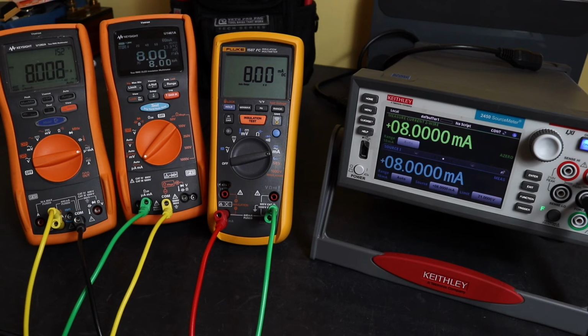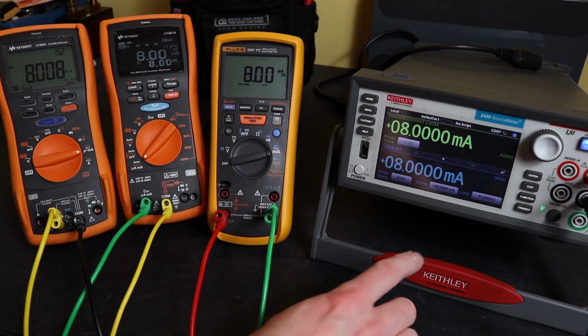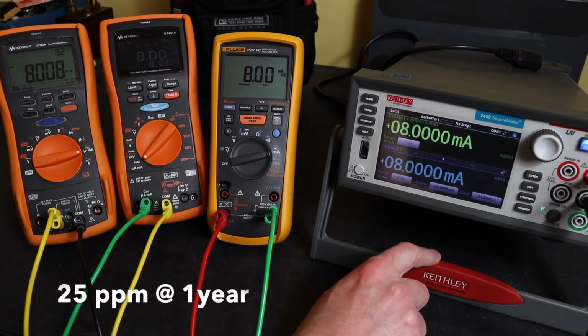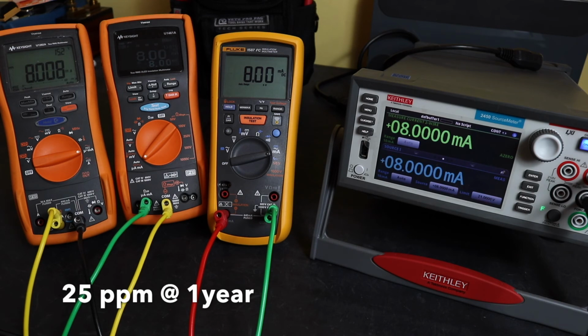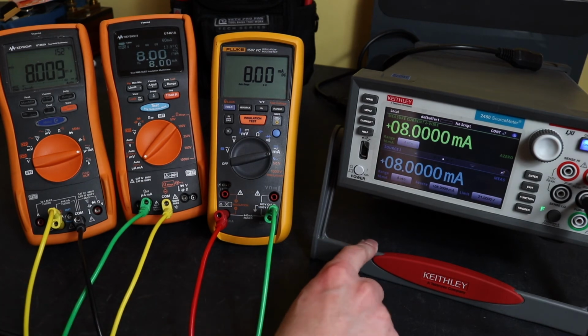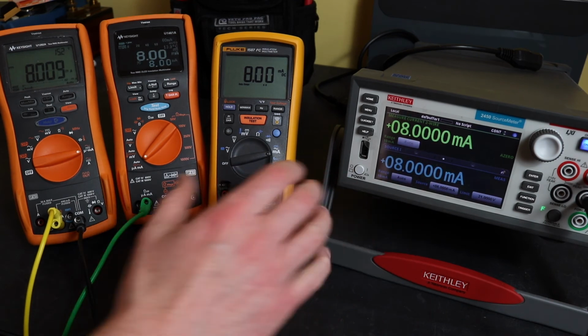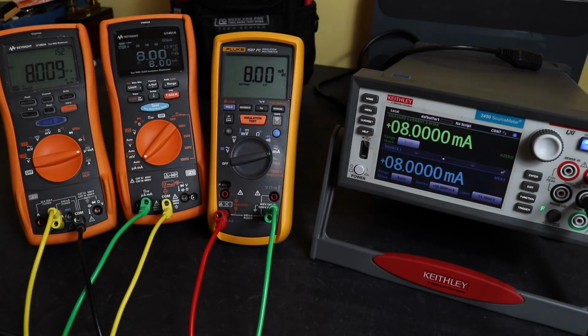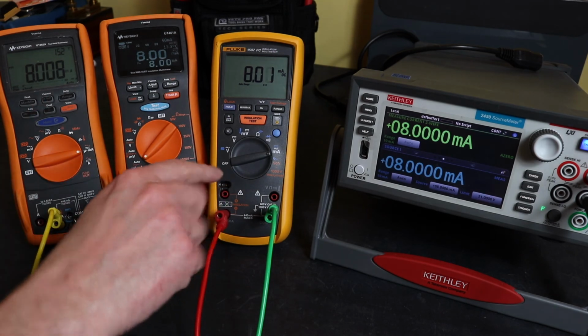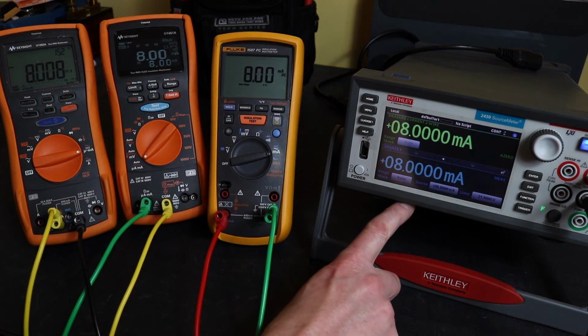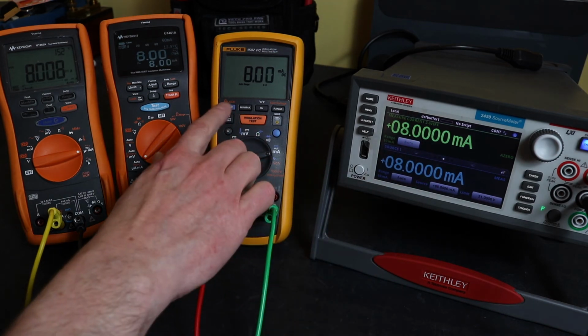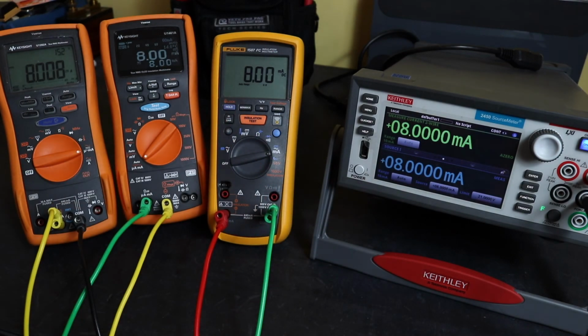The second reason that I can get away with this is I have some very accurate metering here. The Keithley 2450 source meter. I keep that independently UKAS calibrated. It costs me an absolute fortune because it has to go to Germany for that calibration. And I can check any instrument I've got against that meter at any time I feel like, and verify that the meters are reading okay. And what I have here is the 1587. I'm kicking out 8 milliamps on the SMU, and you can see I'm reading exactly 8 milliamps on the 1587 there.